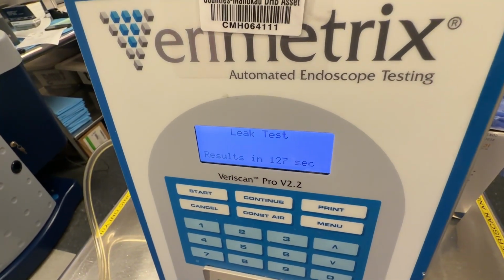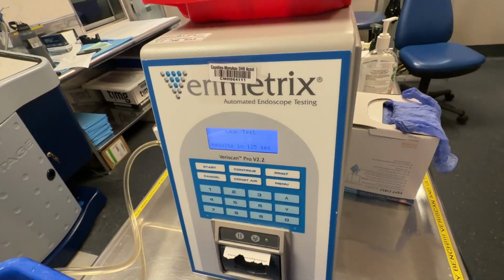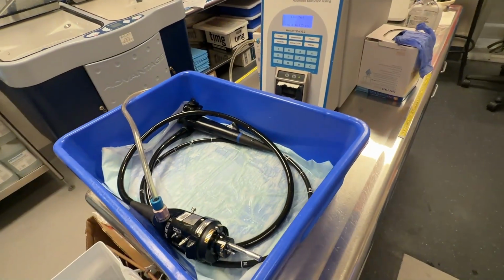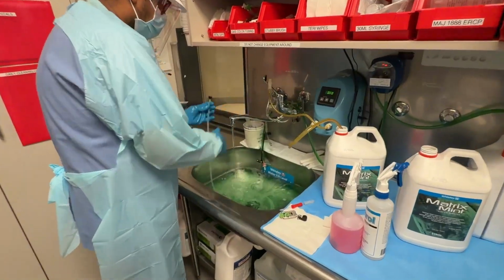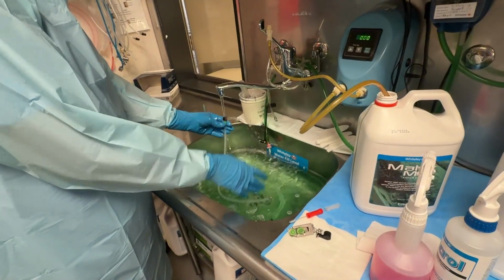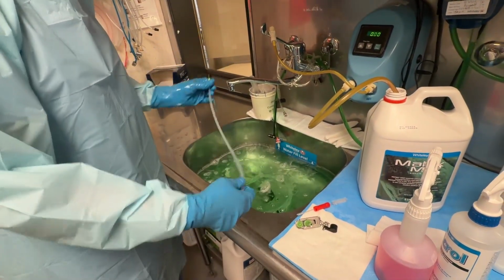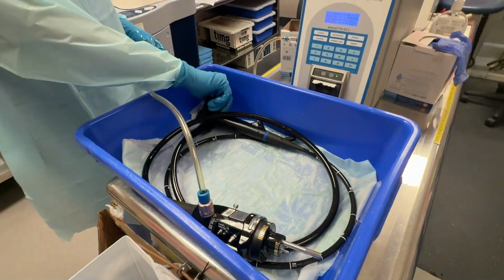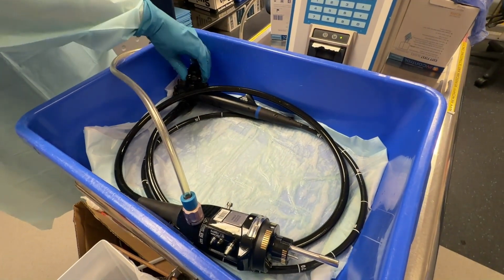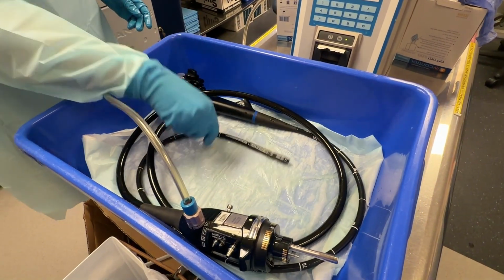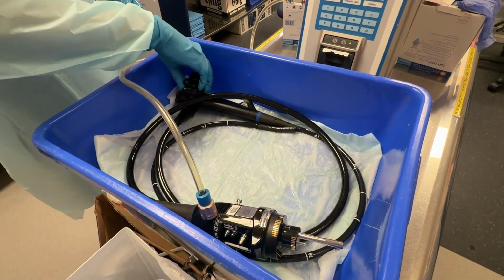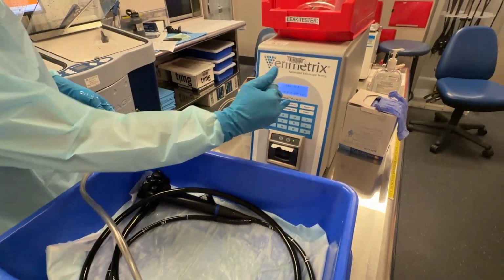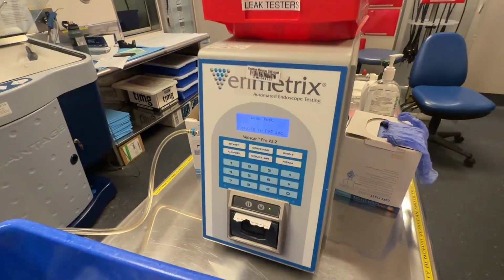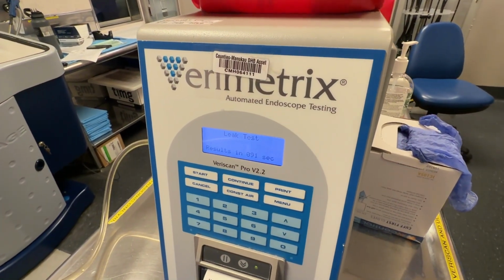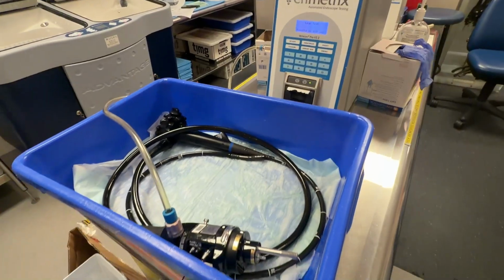So before the manual cleaning, there is a pre-cleaning that happens at the bedside, done by the nurses. That is done immediately after the procedure. So the exterior of the endoscope is wiped, and detergent or water is suctioned through the channels to prevent debris. So right now I'm checking the leak test. The endoscope is tested for any damage or hole. We will do the fluid test and leak test.